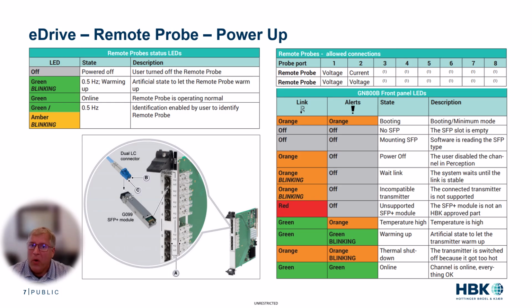While the remote probes are warming up and establishing communication with the mainframe, you'll notice the change in the LED status on the remote probes and the front panel of the GN800B fiber optic receiver card. In fact, it's going to take about 5 minutes until both LEDs on the GN800B fiber optic receiver card turn green, indicating the remote probes are online and everything is okay. Please make sure that the first port on the receiver card is from the voltage probe and the second port on the receiver card is from the current probe.